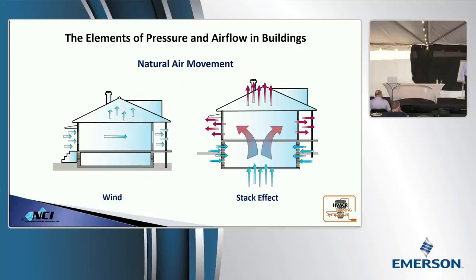What are you heating? The air. You're heating the air. That's what creates the stack. That's what creates the draft in the building. A common misconception in our industry is that we have to heat the flue to create the flow. We don't have to heat the flue. We have to heat the temperature of the air inside of it.